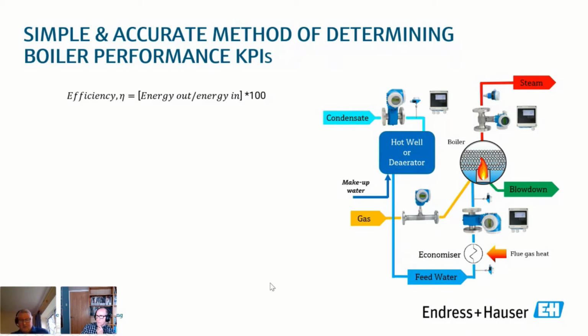So it's a very simple method of calculating the performance. There are all sorts of efficiencies associated with boilers, but it's the fuel to steam efficiency that's the most useful. This has a direct bearing on the costs. Absolutely. And if we look at kilowatt hours as an energy unit, and we try and get everything in those units, then the calculation becomes really simple. So if we look at the kilowatt hours in the steam, again, we've got to convert volume to mass and mass to heat.